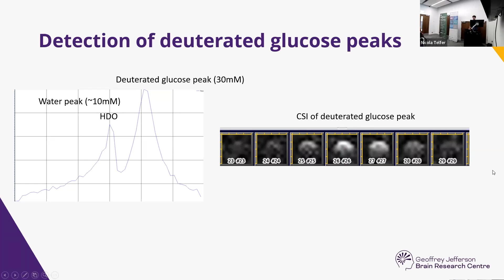Okay, so finally, I just wanted to show an example of some of the data we collected at the end of the project when we got this coil back from the supplier fixed. And this shows a phantom that contains water and deuterated glucose. And we're able to see here the water peak, which was at about 10 millimolar, and a deuterated glucose peak at about 30 millimolar, and an image of this deuterated glucose peak. And this is scanning across the frequencies. So as we move across this peak, we can see the signal of this circular test object increase and then decrease again.